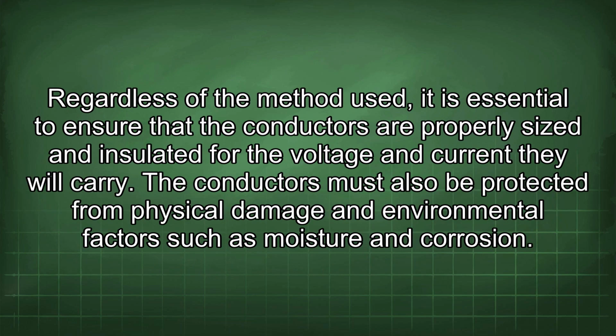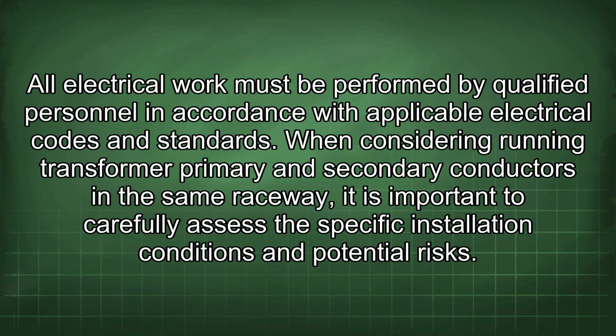Regardless of the method used, it is essential to ensure that the conductors are properly sized and insulated for the voltage and current they will carry. The conductors must also be protected from physical damage and environmental factors such as moisture and corrosion. All electrical work must be performed by qualified personnel in accordance with applicable electrical codes and standards. When considering running transformer primary and secondary conductors in the same raceway, it is important to carefully assess the specific installation conditions and potential risks.